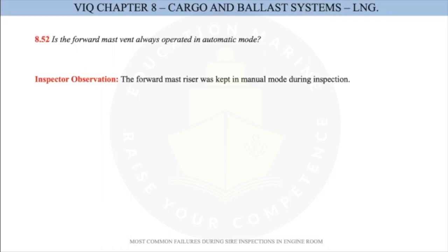It will happen only if this vent riser valve will open, if it's on auto mode. If it's in manual mode, it will not open. That means that you will skip your first protection. And this is a very important thing. It should be in auto mode.